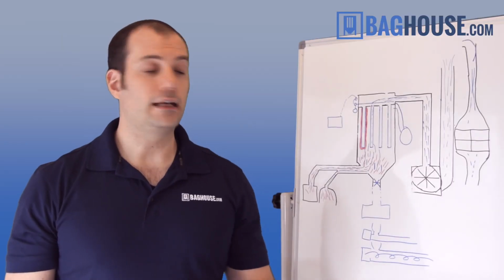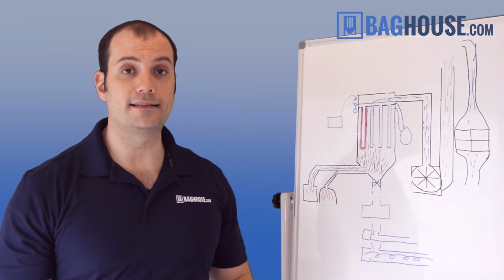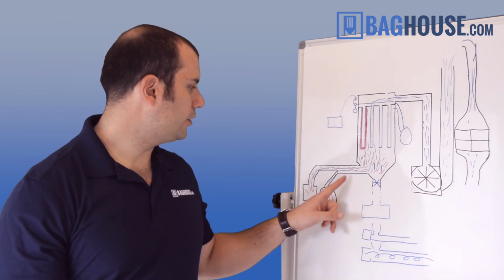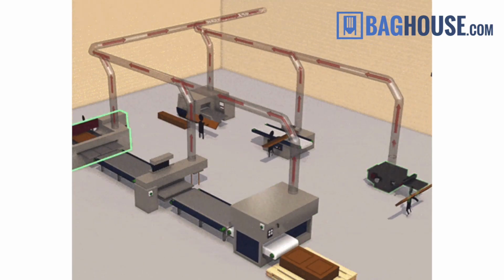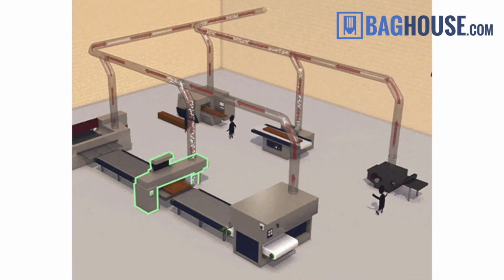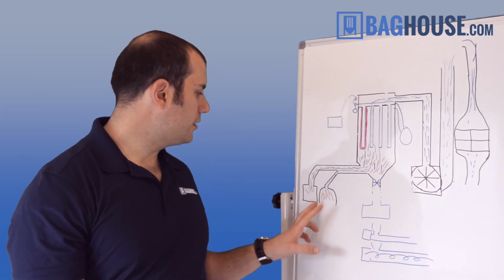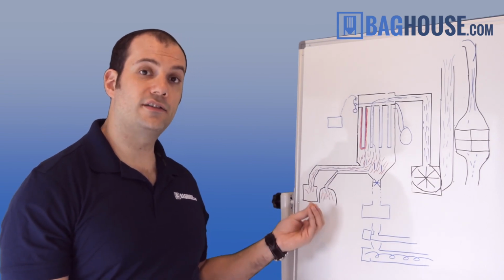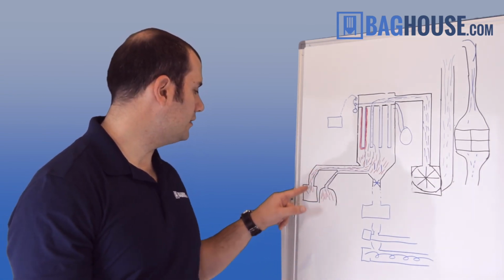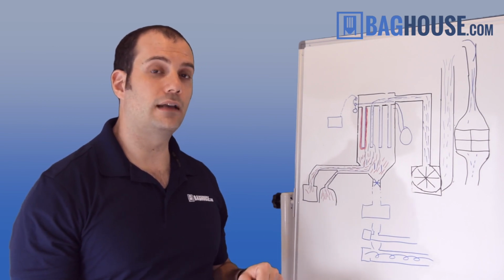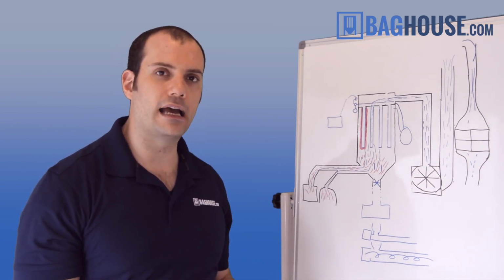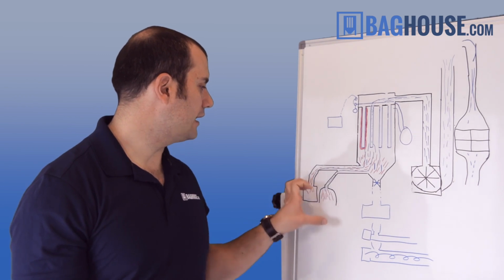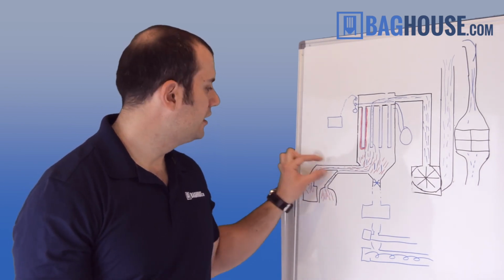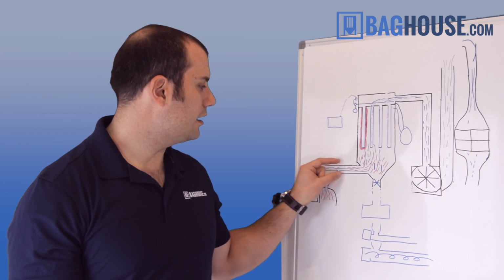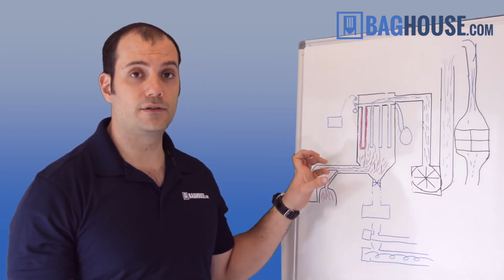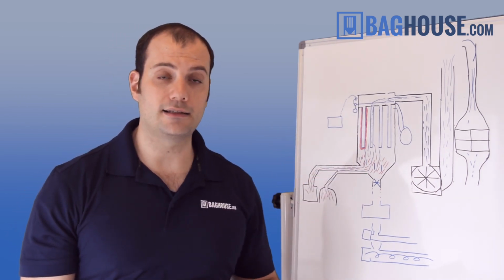So the first part is actually the ductwork system itself. You'll see here, ductwork for a dust collection system can have multiple pickups or drop points. Sometimes it can just be one. These usually take the form of either some kind of hood over a dust source, or sometimes it's ducted directly into a piece of process equipment and it connects directly to the machine or apparatus. Regardless of how it connects, we then have our duct branches that come together and form the ductwork trunk line, or the main branch of the ductwork, that then goes back into the dust collector.